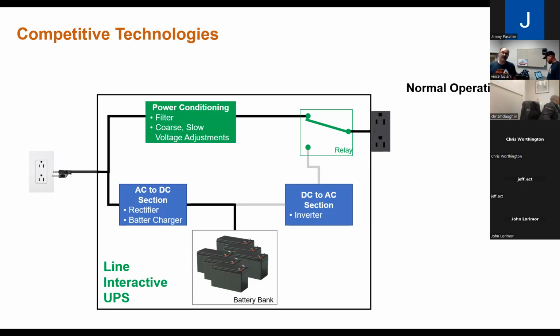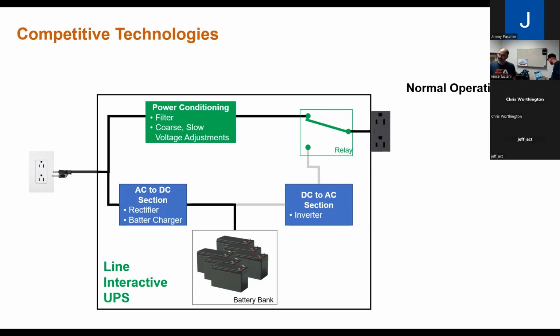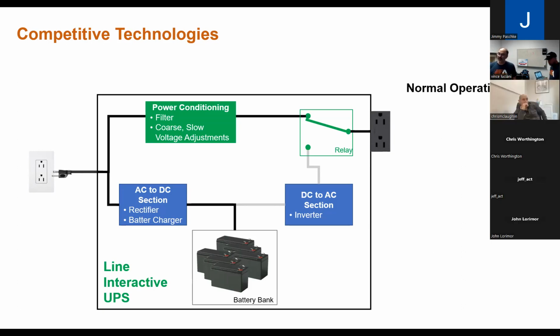You've heard a lot about line interactive UPSs. This is the kind of structure of what a line interactive UPS looks like. It has similar characteristics, it has the rectifier or battery charge circuit, it's got the inverter section in there. But as you can see, there's a relay in there, in that upper right corner. Most of the time, a line interactive UPS is just passing power from the input to the output. It may go through some cursory power conditioning, but it's not the greatest power conditioning. It might have a filter in there.